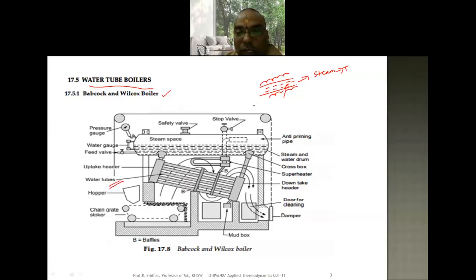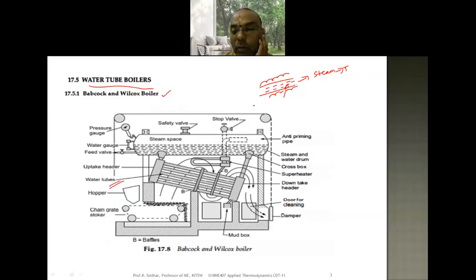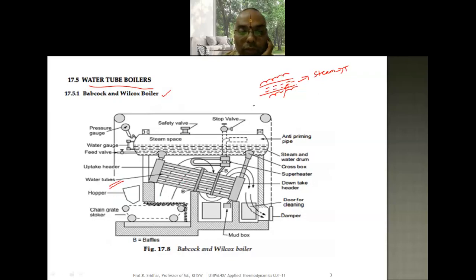The water tubes are inclined to the header — they are not horizontal and not vertical, they are inclined. The inclined water tubes are arranged in the Babcock and Wilcox boiler for effective circulation of water and effective heating, which increases the efficiency of the boiler. Water flows inside the tubes, and the grate is the surface on which coal is burned.